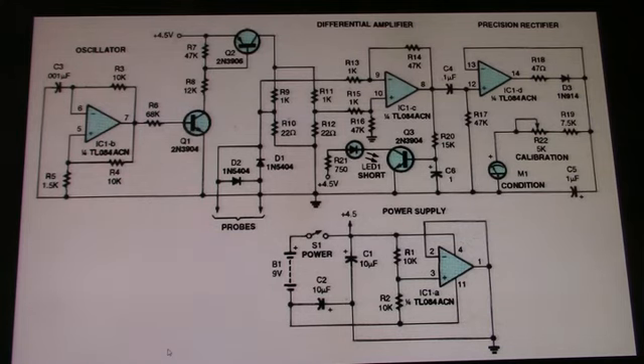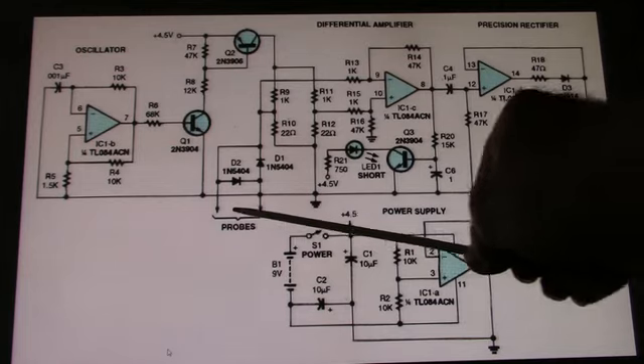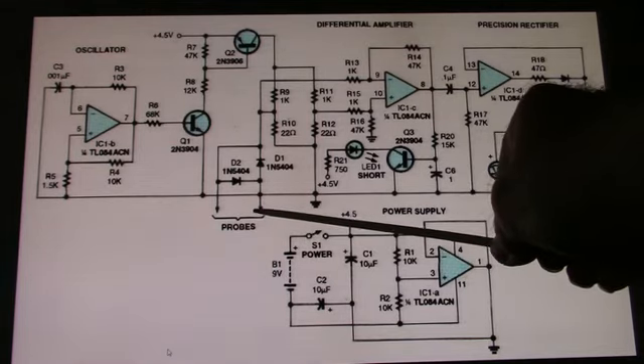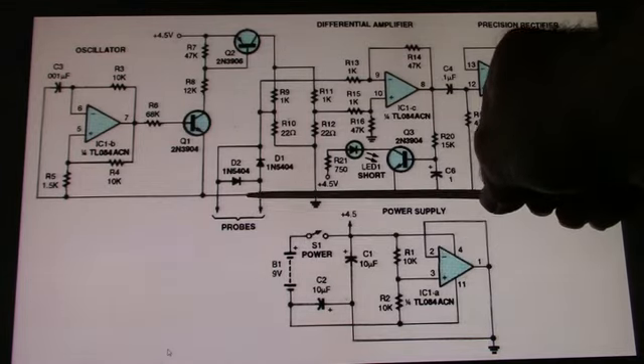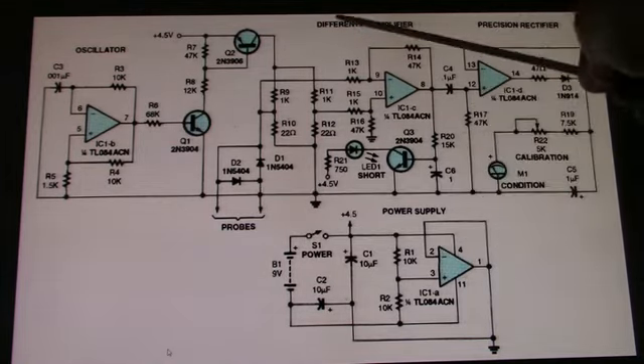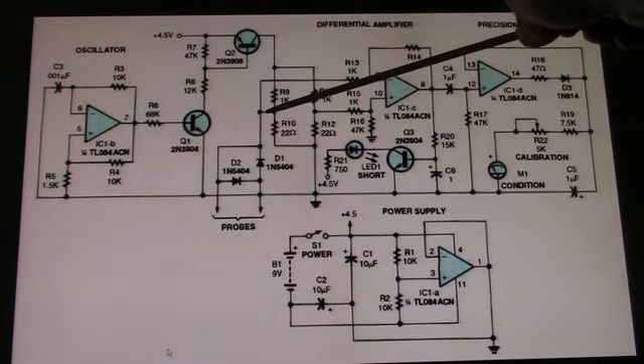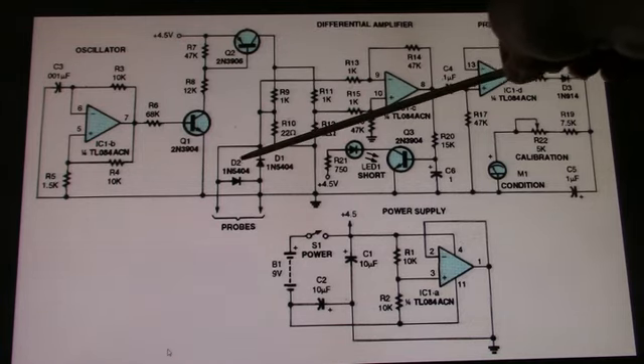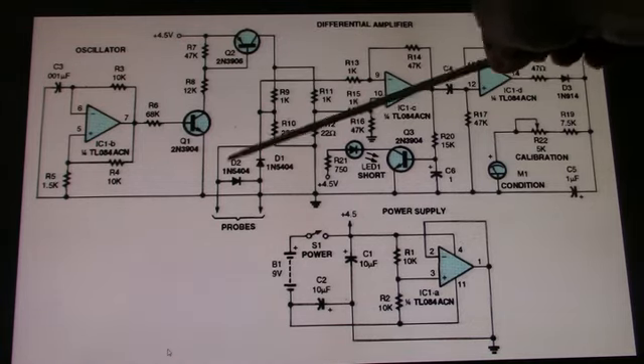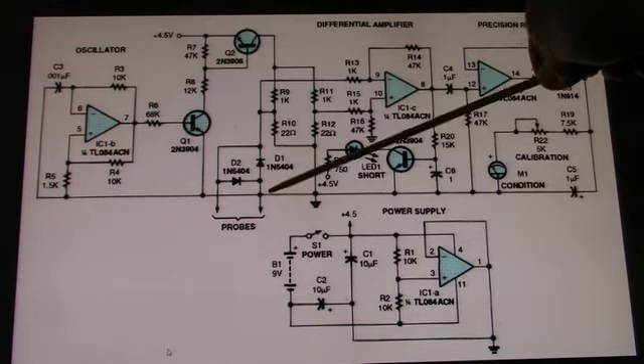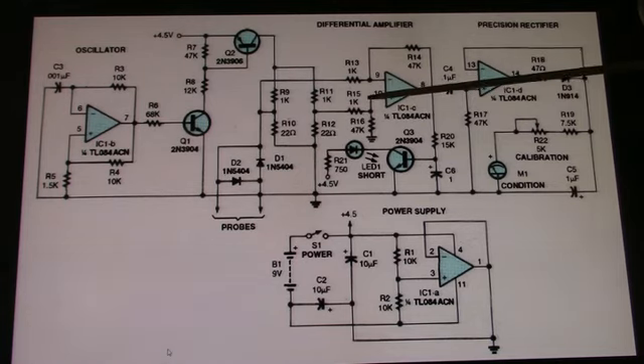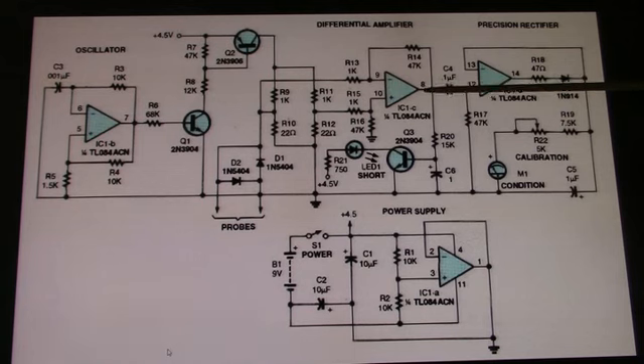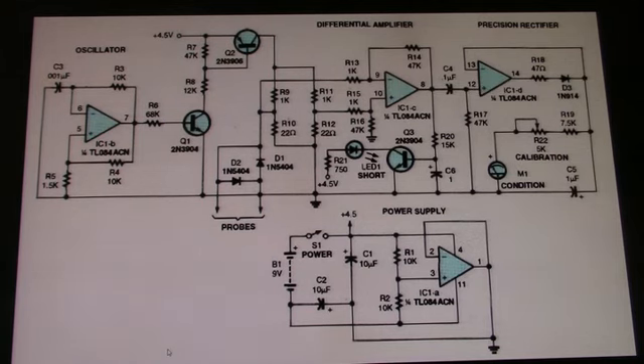You got two probes here that go across the capacitor. If you leave these probes open, since this level here is too low to bias these diodes, they're basically out of the circuit. In that case, the bridge is balanced and there's no output on pin 8, and the meter is going to register zero.